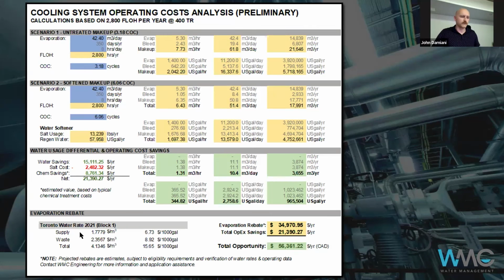There are lots of formulas we can go through when talking about water treatment, but there's no real magic formula for benchmarking or savings. It's really looking at each system individually, modeling it, and comparing where we're at to where we can be. If you're not operating optimally, we compare it to optimal operating conditions to get a baseline, showing how far off you are. Just getting it back to industry standard will save you money before we even start improving the system, and then we can go to the next level.